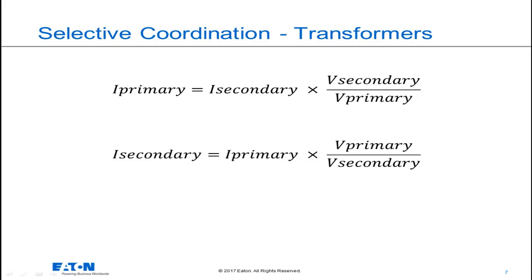These are the two important equations you need to know. Current reflected from the low voltage side of the transformer to the high voltage side of the transformer will always get smaller. Current reflected from the high voltage side of the transformer to the low voltage side of the transformer will always get larger.